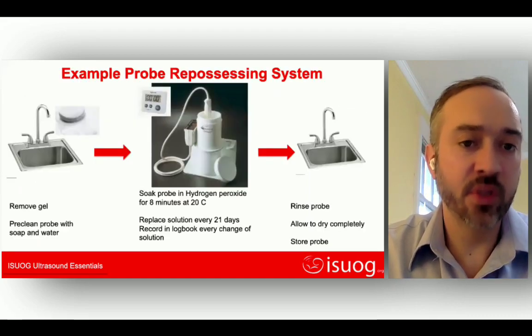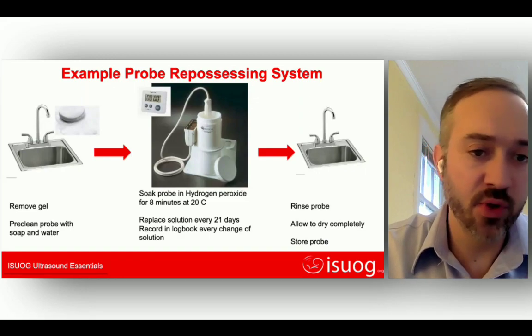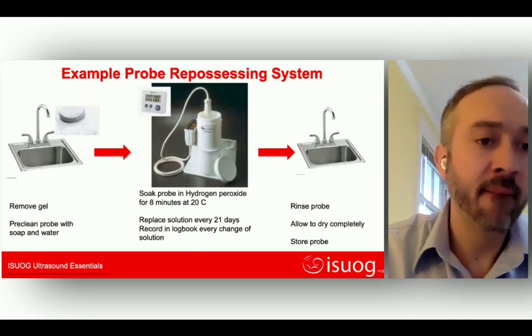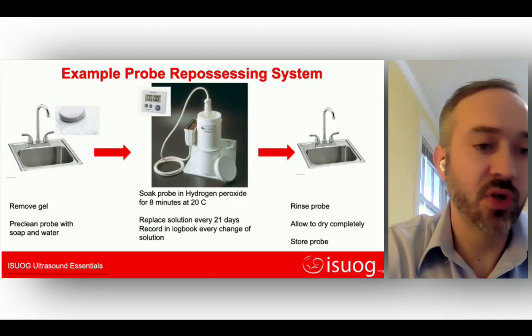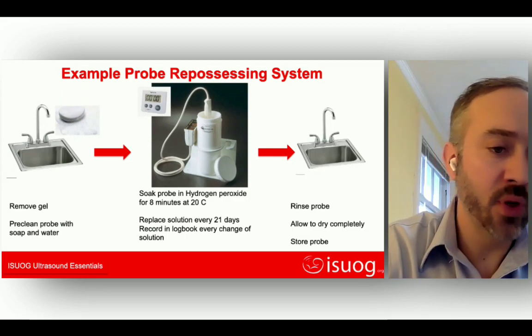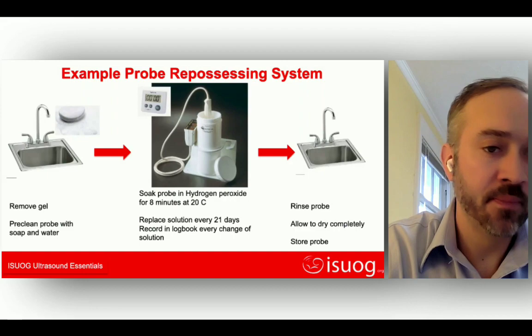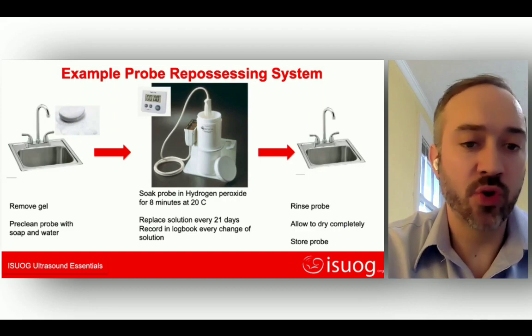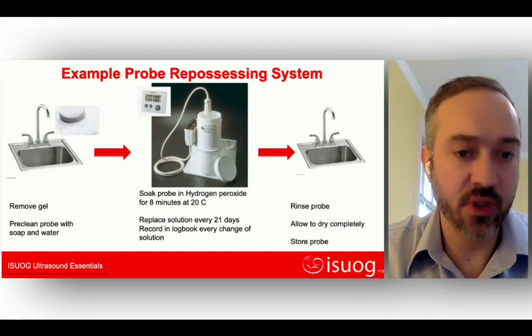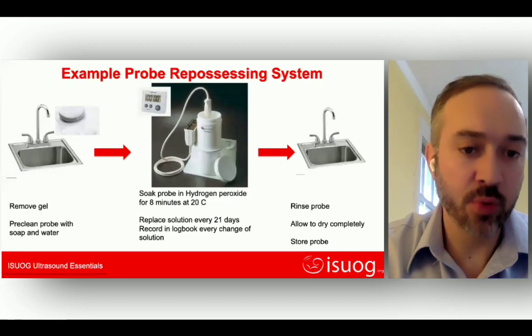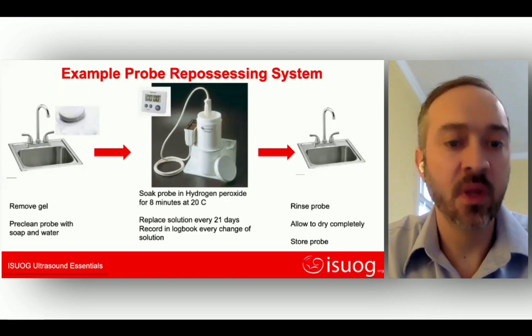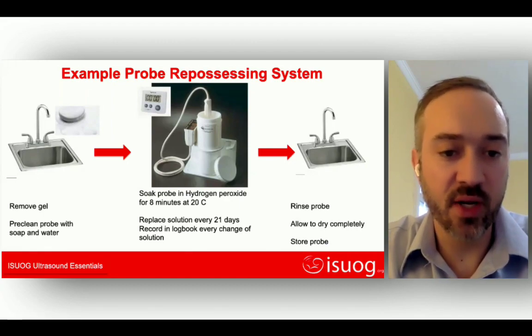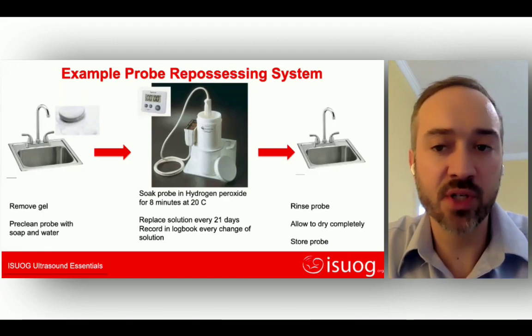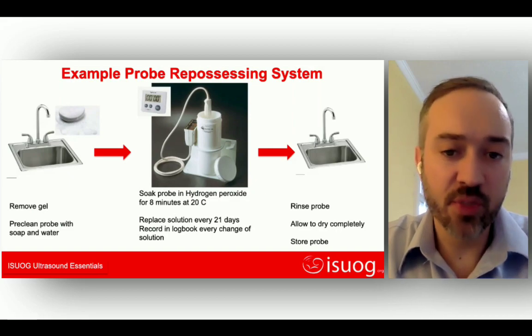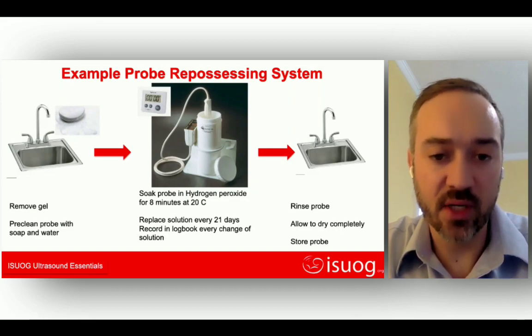Here's an example of a typical probe reprocessing system using a simple soak method. First thing you'd want to do is remove your gel and pre-clean your probe with soap and water. Next, soak the probe in your soak solution. This one gives the example of hydrogen peroxide. Give it the appropriate time and temperature. Replace the solution and keep a log of when it needs to be replaced. Then rinse the probe, let it dry completely, and store the probe.